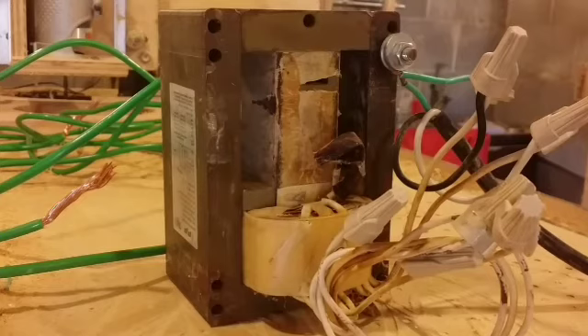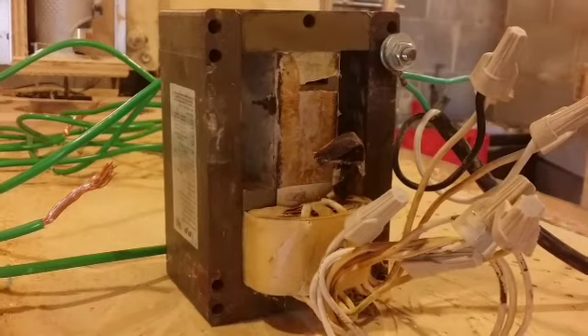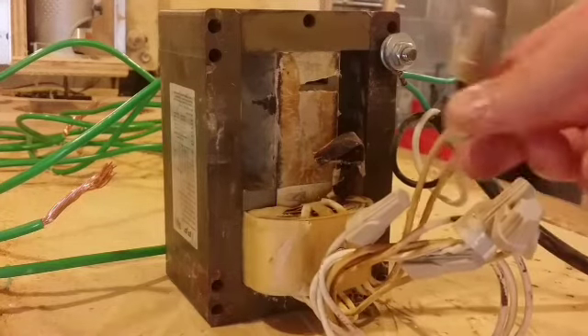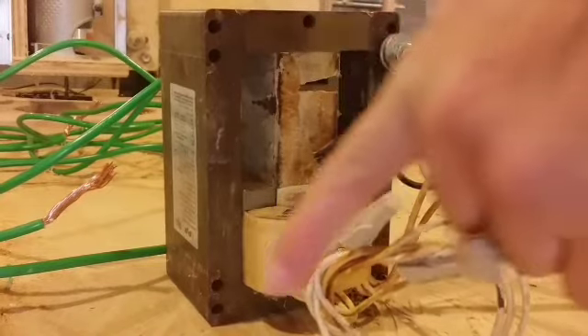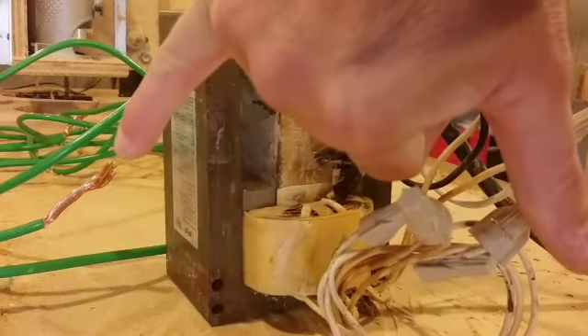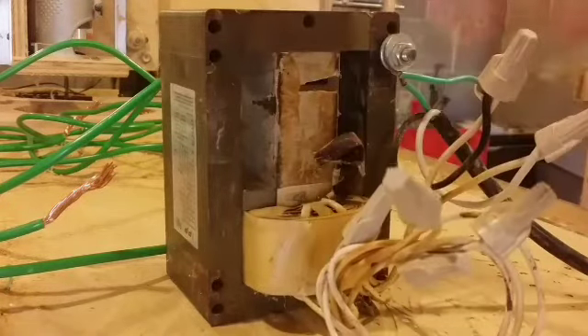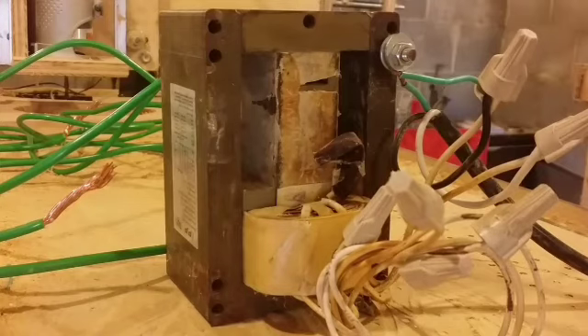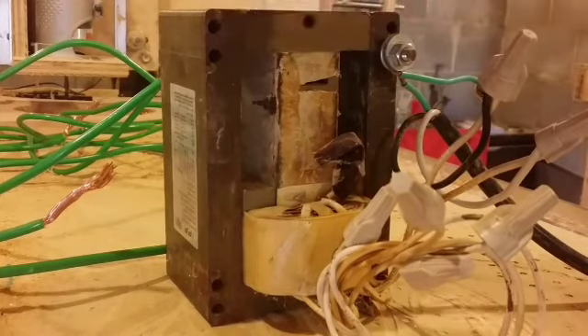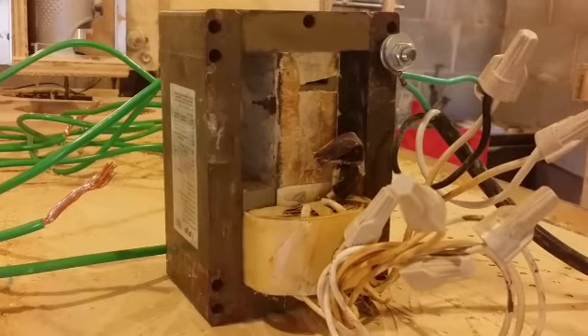The 480 volt tap and the common, there's also a common, this is a common tap, the common end. The 480 and the common are actually on the opposite ends of the coil. That's the whole coil, 480 and common. Everything else, all these other voltages are somewhere in between, tapped. In other words, the auto transformer is a single winding on a core. It's a single winding with the common and 480 being at each end of the coil.